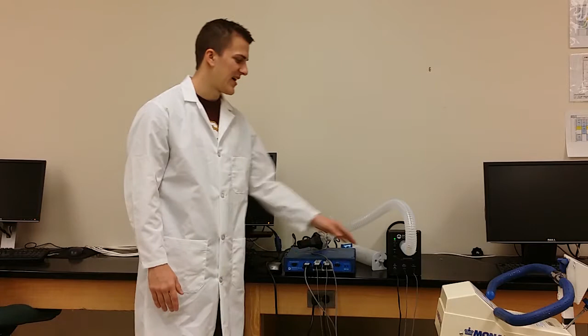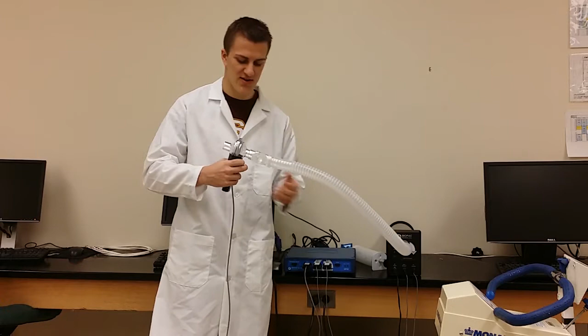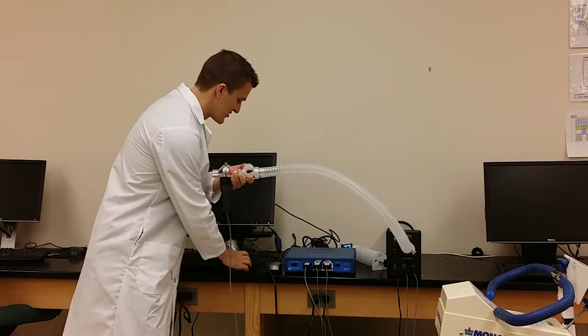Next, you want to make sure all the transducers are plugged into the correct channels. The first one, you want to have the spirometer in channel 1. The second one should be the O2 line in channel 2, and then in channel 3 you should have your CO2 line. As far as the gas analyzer setup, you want to have your hose coming out of the big port right here over to the inlet and the spirometer. And then when you are ready, you're going to put the mouthpiece attached as shown here, not directly connected to the spirometer, like some people think. It's counterintuitive, but you want to make sure you have it set up like so, and it should also be indicated on your instructions.